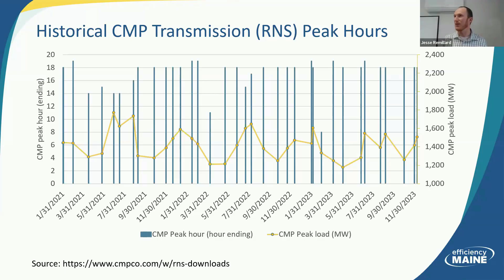Folks in Massachusetts have been doing this for quite a few years. There's a study referenced here where the participants - this was one of the primary revenue streams that participants were going after - and they were largely successful in deploying their battery systems during this monthly peak hour. You see above 80%, and there were a number of participants, typically looking at 4 to 6 discharges, maybe up to 10 discharges per month in order to hit that hour.